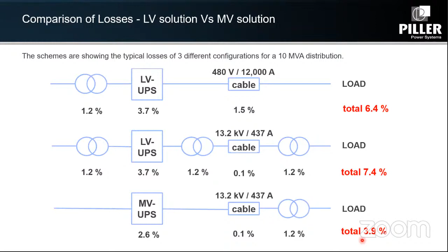What we are saying is you could simply put a medium voltage configuration. This is the loss from our UPS system. We're talking about online, not eco mode, energy management, whatever you want to call it. It's up to 97.4% kind of efficiency, 98% efficiency, depending on the block size. You can power the facility directly on a medium voltage, just step it down inside the building, and you can eliminate a huge amount of loss.